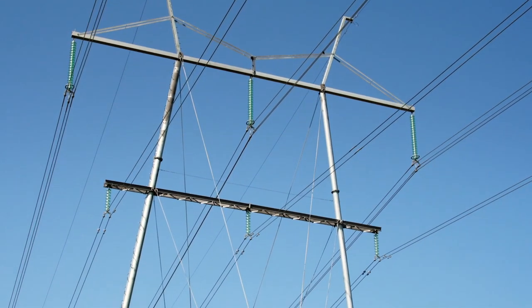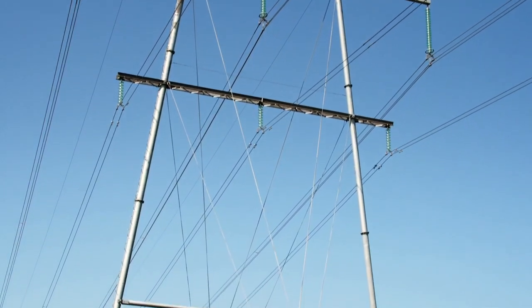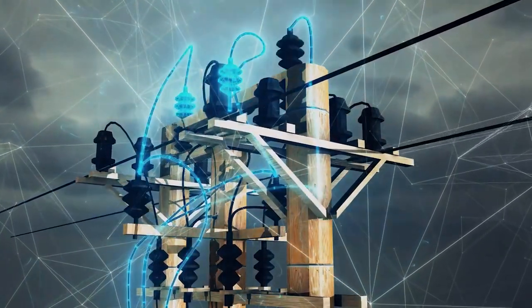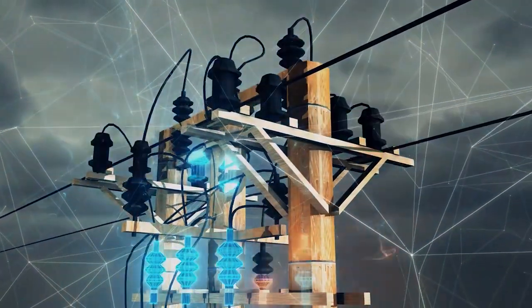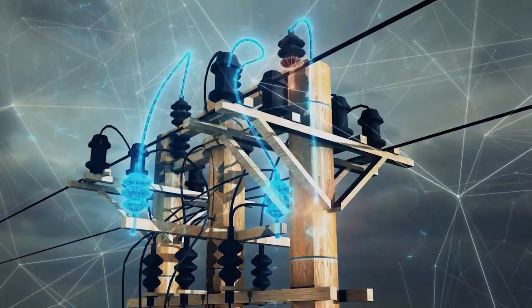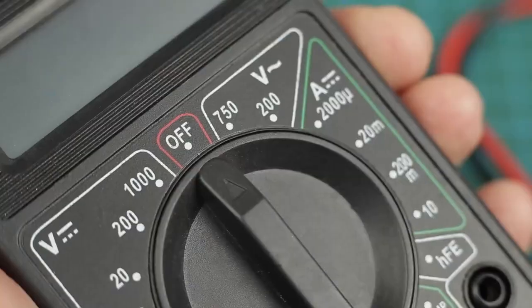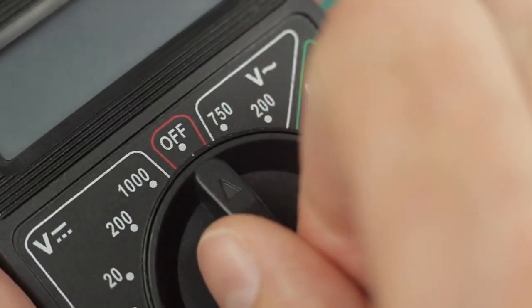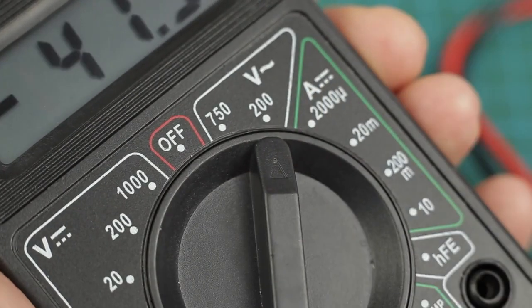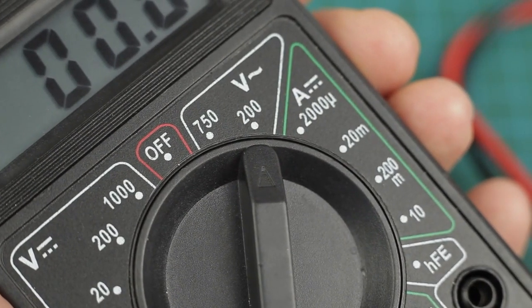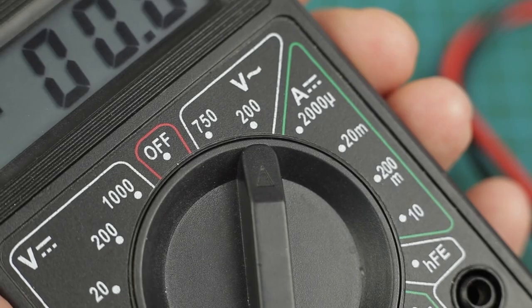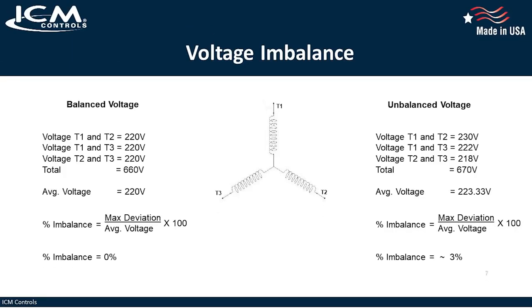We've all heard the term dirty power. This is a common problem here in the US because of our aging power grid. That's why it's critical to always check your supply voltage when installing a piece of equipment. You can use your Fluke meter to measure the voltage across each phase. If they're in balance, lucky you. If they're not in balance, then you need to determine how far out of balance they are.